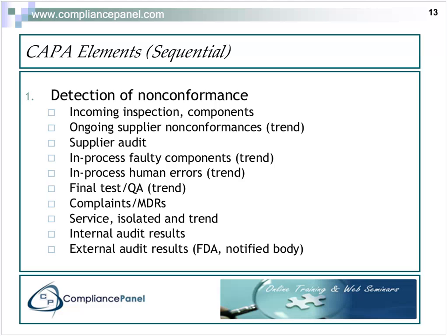If an off-the-shelf component comes in and it's not a critical component, not that that definition is underscored by the FDA anymore. When I say critical, I mean important. It's an off-the-shelf item. It's just a connector that we use. It's just a piece of tubing that we use. If we receive a nonconformance, we will not necessarily perform an investigation and a corrective action. All incoming items are looked at from an ongoing supplier nonconformance area.